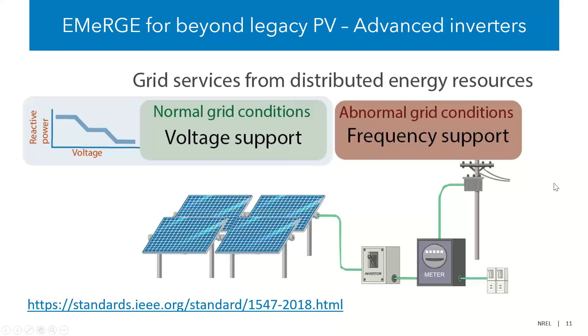Advanced inverters can inject reactive power as a ratio of active power being generated, referred to as fixed power factor, or they can identify how much reactive power to inject based on the voltage at the point of interconnection, which is called volt-var.